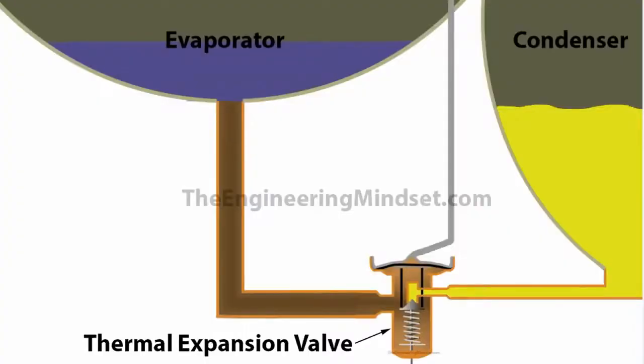So the thermal expansion valve is very similar to the pilot operated one, except that it hasn't got the main expansion valve there. The thermal expansion valve is the main valve in this type. So again, we've got the capillary tube rising up and connecting onto the suction line to measure the superheat, and we've got the refrigerant in the condenser, which will flow through, is being held back currently by the valve head, and once released, that will flow then off into the evaporator.